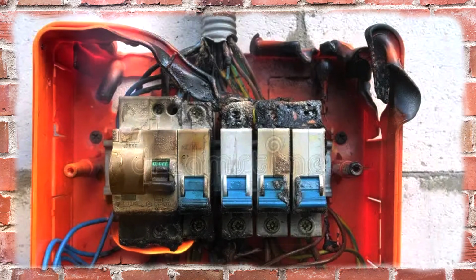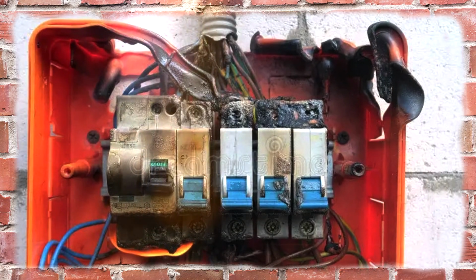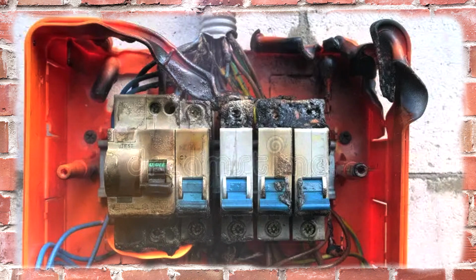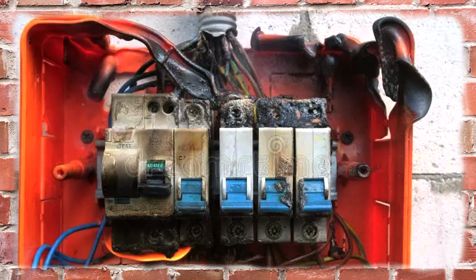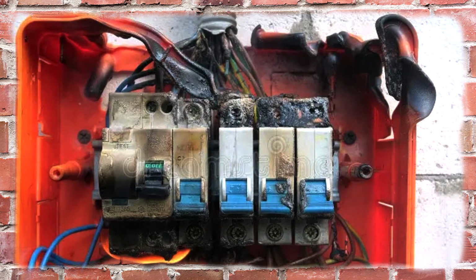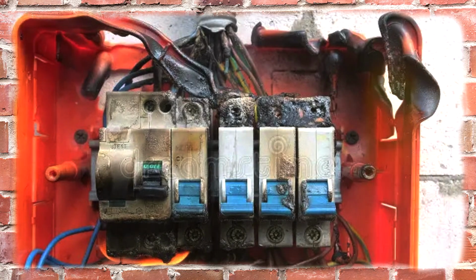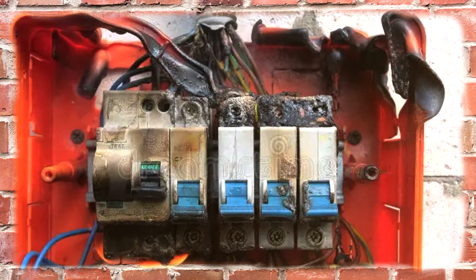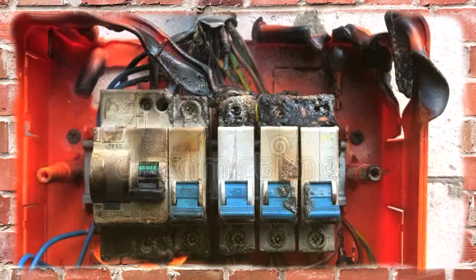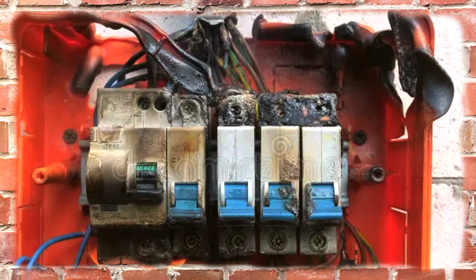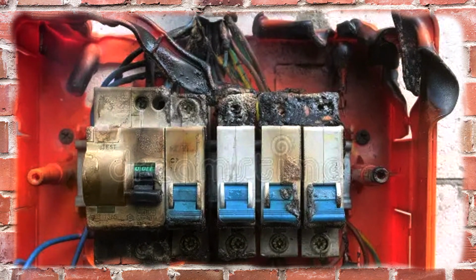where PUE and European norms require neutral and ground separation after the main device to prevent ground current flow and false RCD trips. In the US, neutral and ground bond only at the main panel, strictly separate elsewhere, or leakage current could bypass via neighboring ground wires, causing GFCI failure.